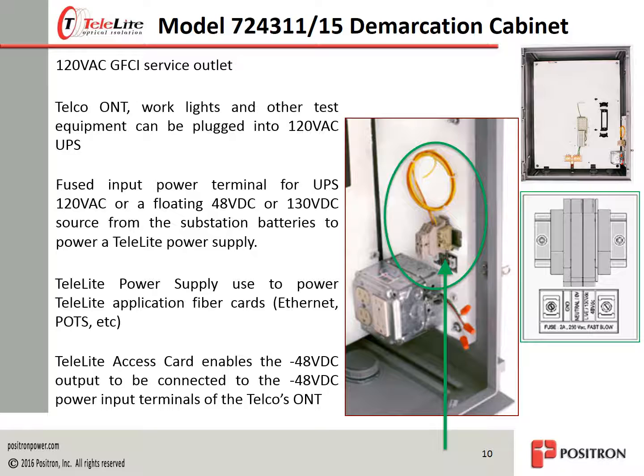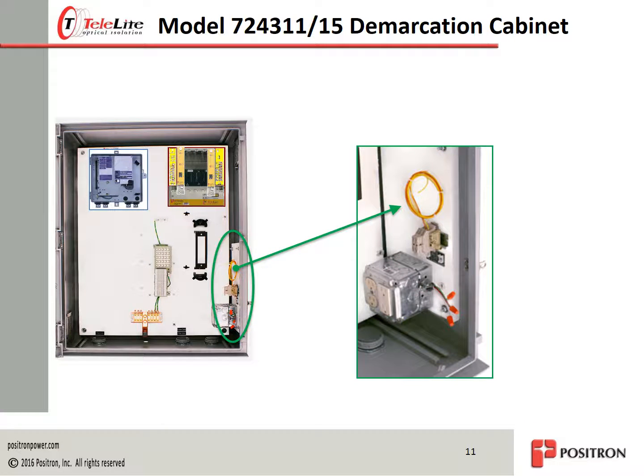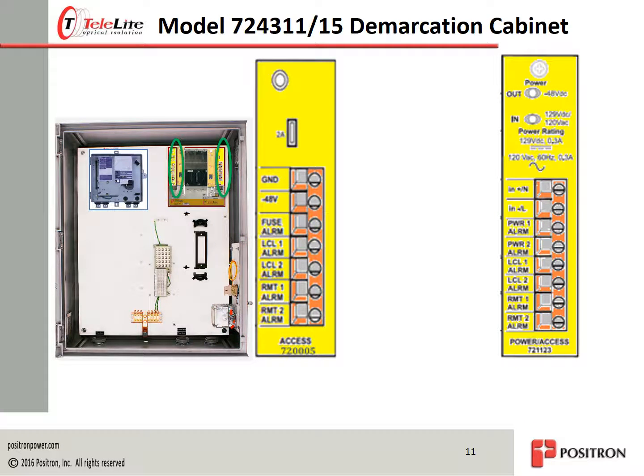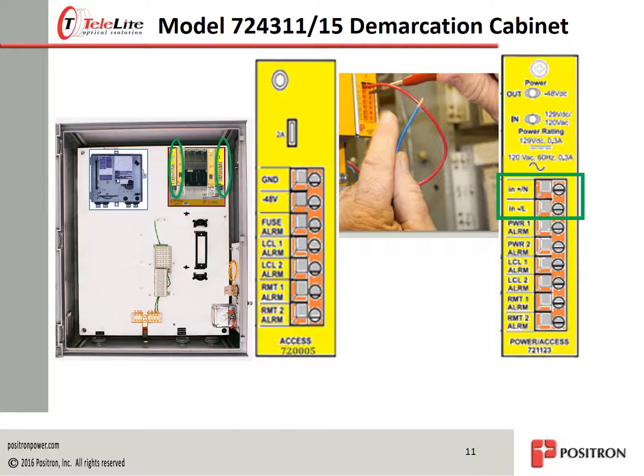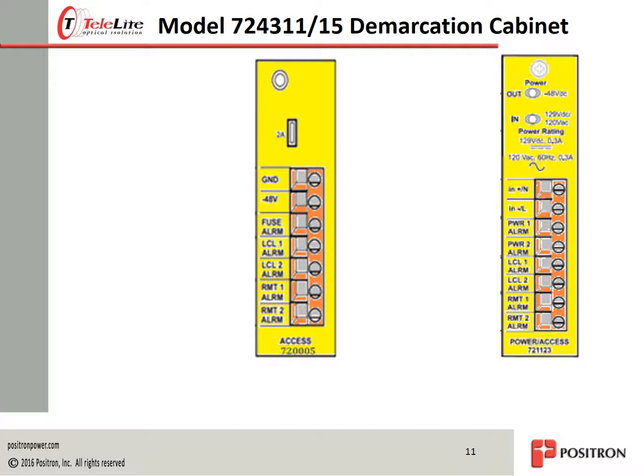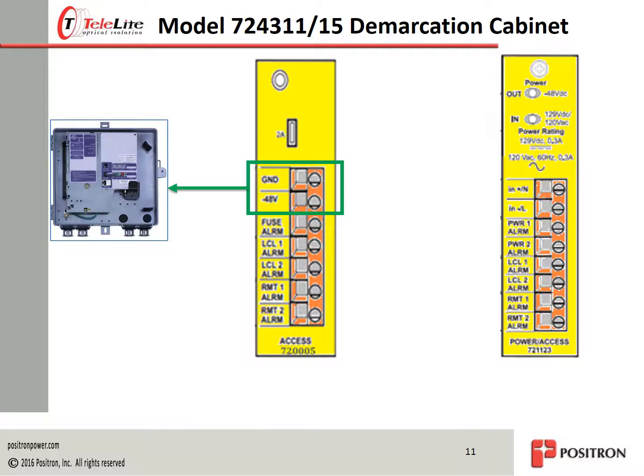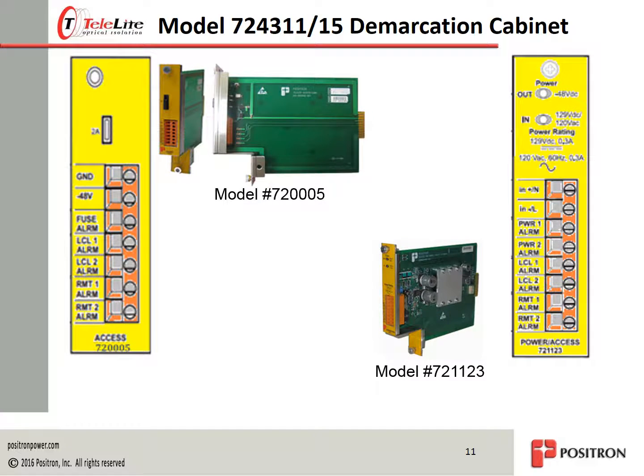Pre-installed conductors on the fused power input terminal block can be connected to a TeleLite plug-in power supply. The minus 48 volt DC output of the TeleLite power supply can be expressed to power the ONT using the TeleLite access card. The pre-installed conductors from the fused input power terminal block feed into the input power screw terminals of the TeleLite power supply. Minus 48 volt DC output voltage can be sourced from the faceplate screw terminals of the TeleLite access card to power the telephone company's ONT. The TeleLite power supplies and access card share the same form factor as the TeleLite optical application cards.